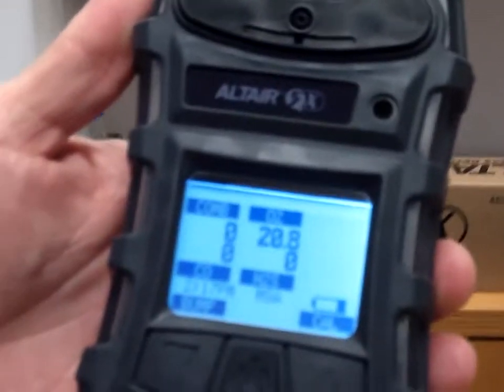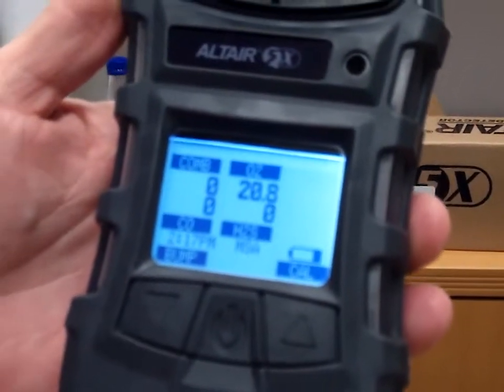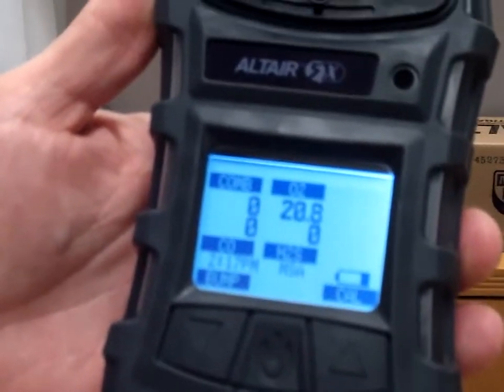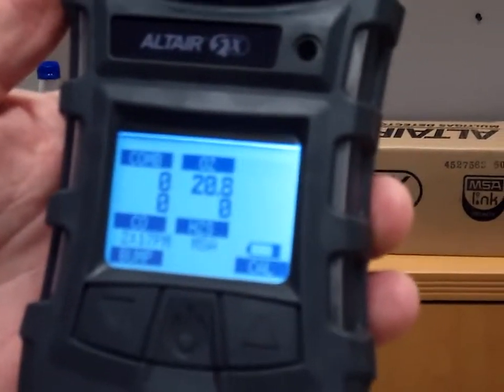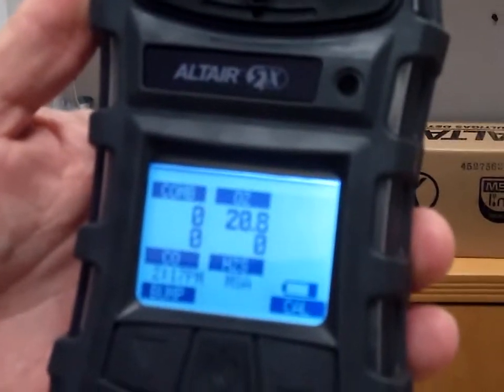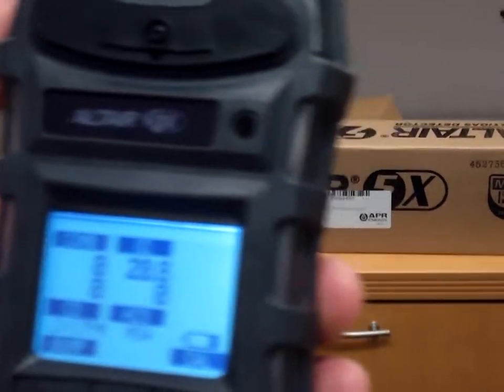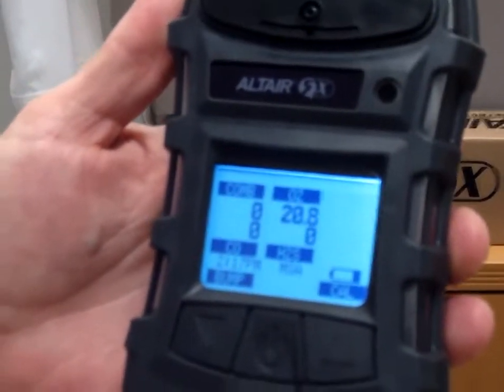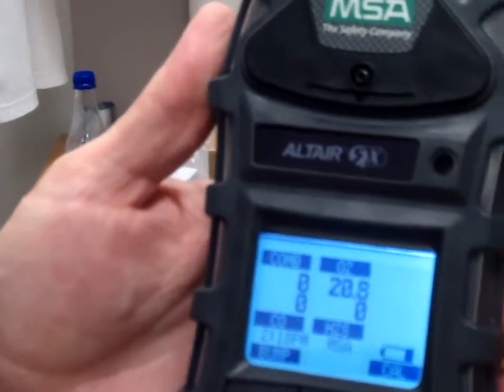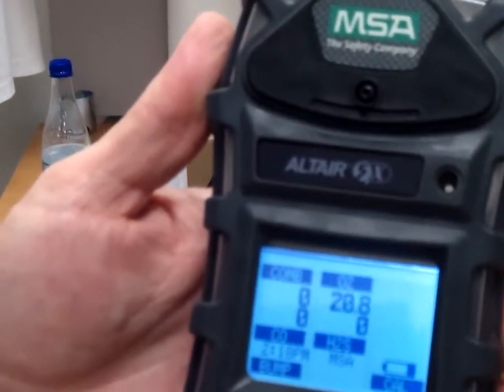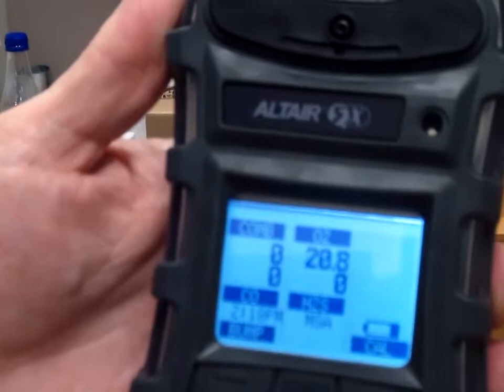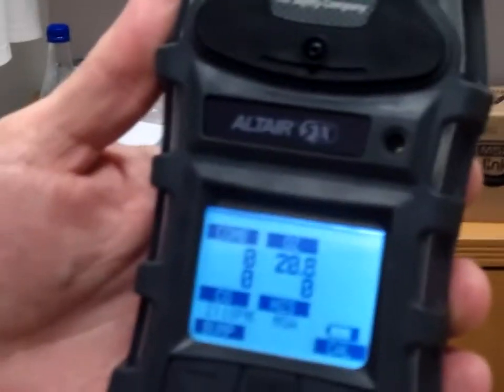Now what it's asking us, we want to do a fresh air setup. You can say yes or no, but if you don't do anything, it defaults to no, and that's actually a better habit, because you want to stay on your calibration schedule. Okay. So if you do a fresh air setup, you're telling the unit at that point that all of the air around you is clear, that it's 20.8% oxygen, and you don't know that for certain, so it's always a good idea to stay on a good calibration schedule. Mm-hmm. And we'll talk about that later.